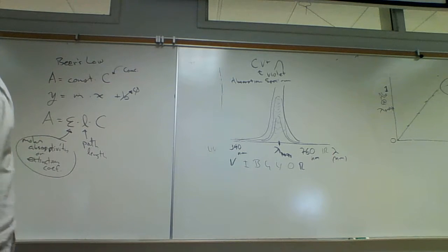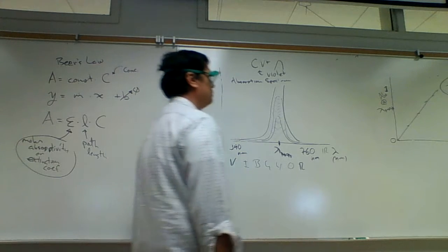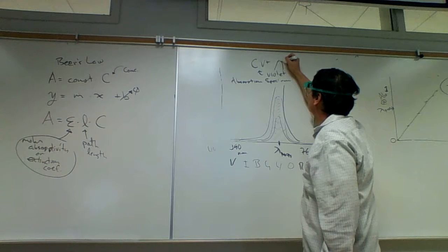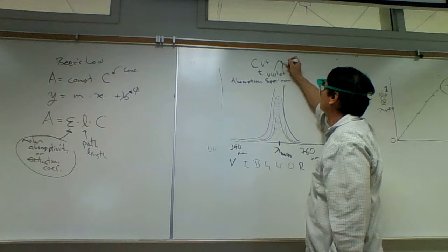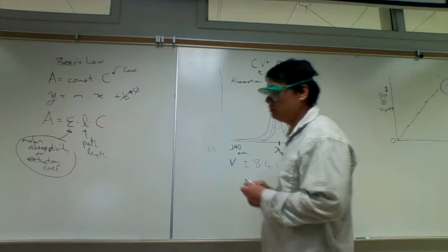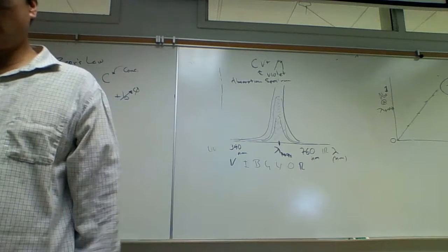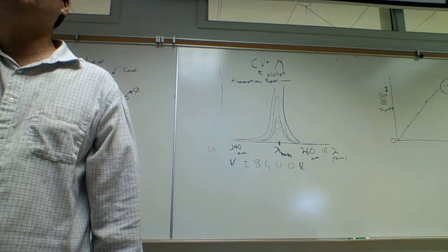So it's slightly different, right? It's always going to be slightly different because of the way this thing picks the peak. It picks it based on the data point. It doesn't pick it based on what we call a curve fit. And so it's not supposed to be moving like that. How many data points make this line? When you see this line, it looks like a smooth, continuous one, but there's gaps, right? And those gaps are at 1/10 of a nanometer.